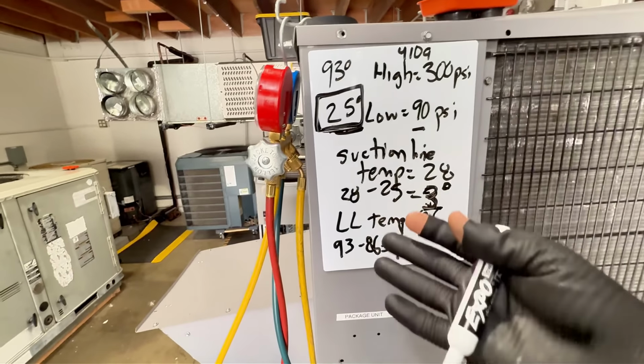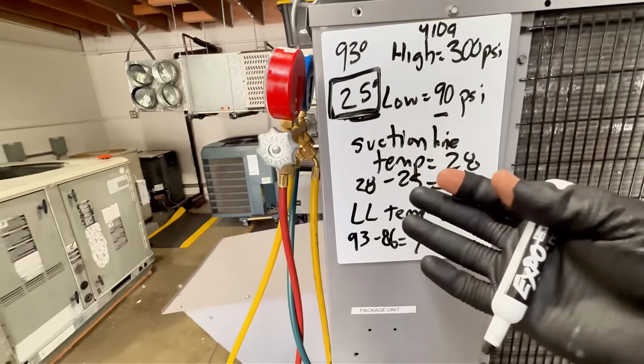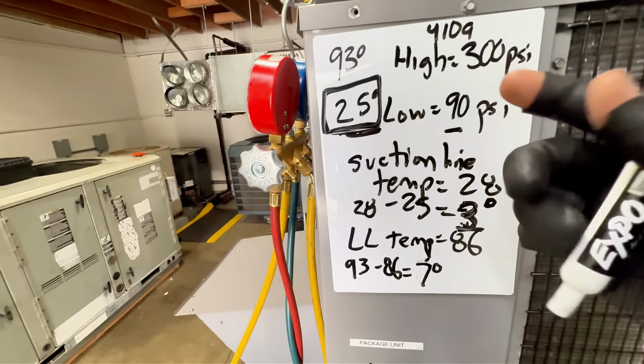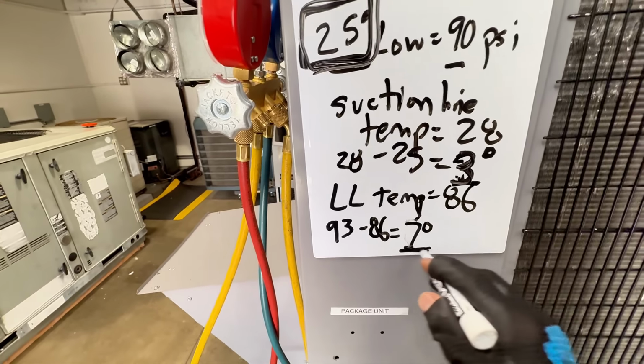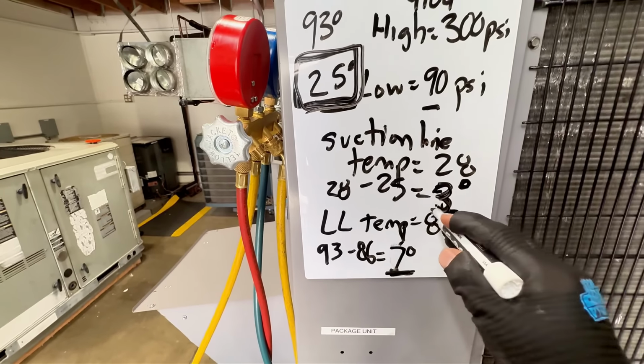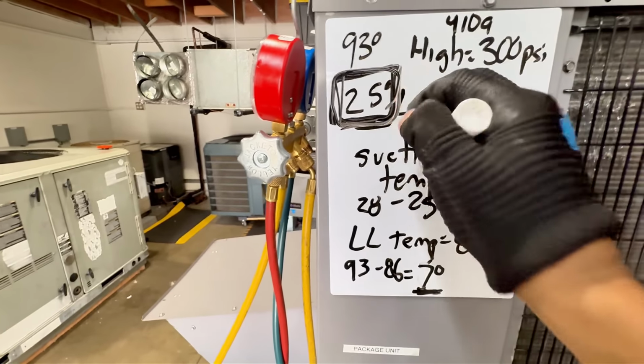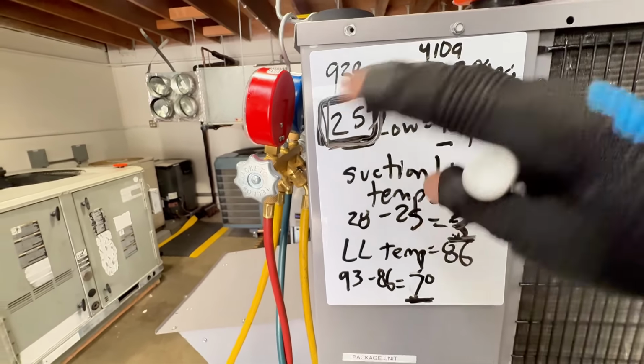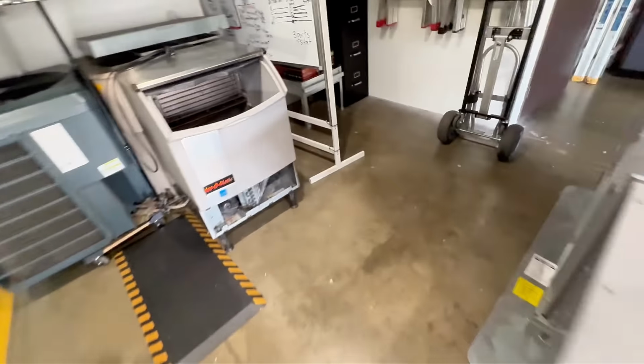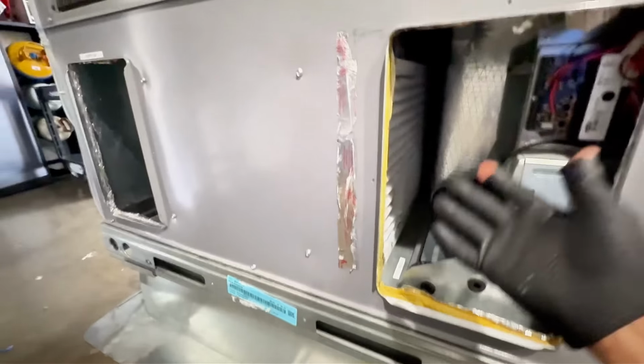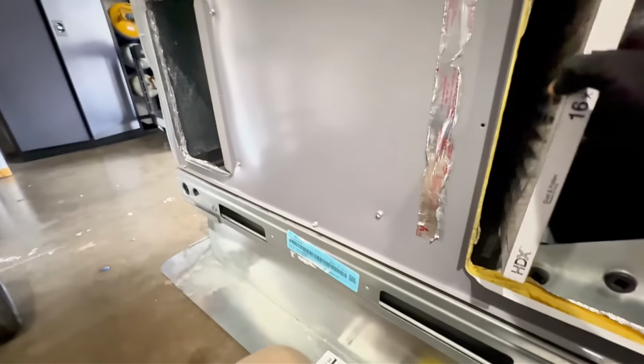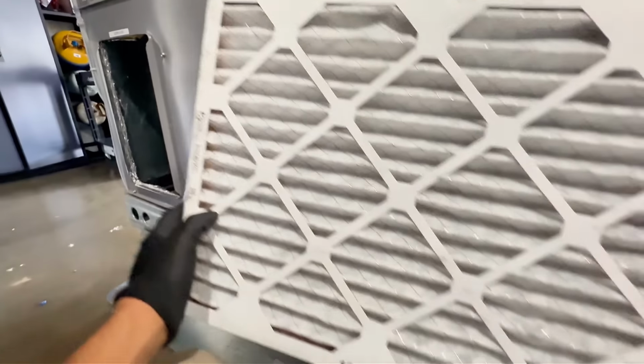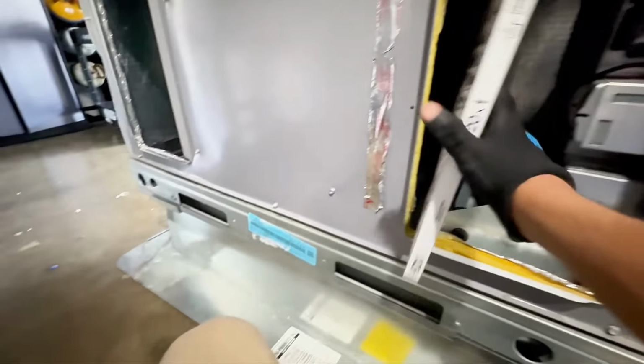Air restriction, dirty filter, closed supply vents, closed return or kinked return ducts. So it's got to be an airflow issue just because of seeing this number. So don't let it trick you. You can be like, oh, I'm good, it's properly charged, 7 degrees subcool. But my evaporator temperature has got to be at least 40 degrees around there, right? Based on the heat load. So now I'm going to be looking for an airflow issue. That's why you always check filters first, right? I don't know if there's an airflow issue or not. It looks clean. Okay. And we're not economizing right now.